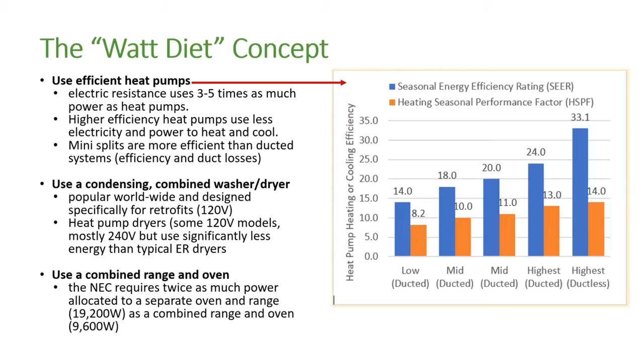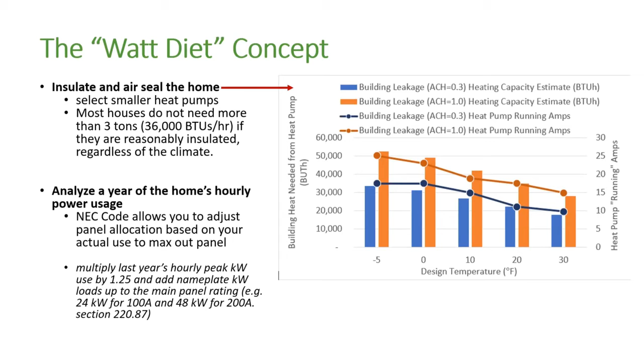This one has design temperature on the bottom axis, meaning how cold your climate gets. I live in the Bay Area, so mine's at the far right, 30 degrees Fahrenheit, and other places get colder. On the right-hand axis is the heat pump running amps, and you can see that as you get into a colder climate, there are more running amps on these heat pumps. The main difference between the two lines is whether your building is tight or leaky for air tightness. Tightening up your building can let you pick a smaller heat pump and have a lower amp load on your panel. Next.